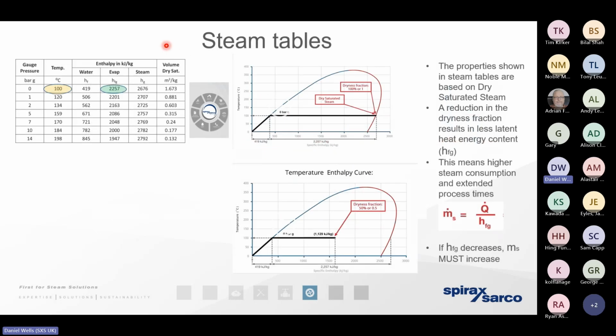So just to emphasize that point, we've mentioned previously that the steam tables only really apply when we've got 100% dry saturated steam, which sits on the red line that you can see here. So if we've got steam that is, I mean, this is an extreme example, 50% dry, 50% wet, you can see we've got 50% of the expected energy present within it. So you can appreciate the extent to which the boiler would now have to work significantly harder in order to satisfy the requirements of our various heat exchangers.